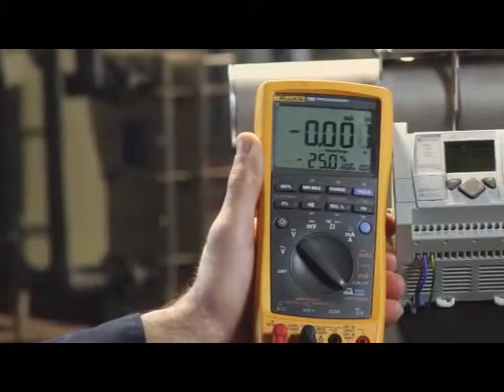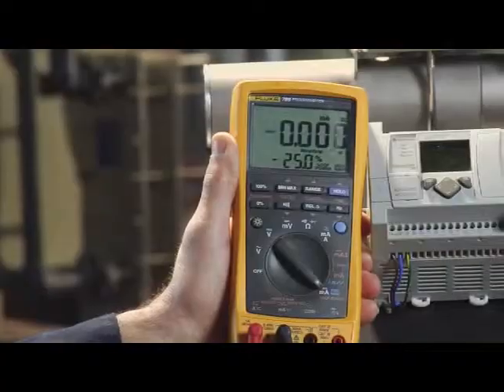It also has a 250 ohm HART resistor you can switch in that will permit communication with a HART communicator.